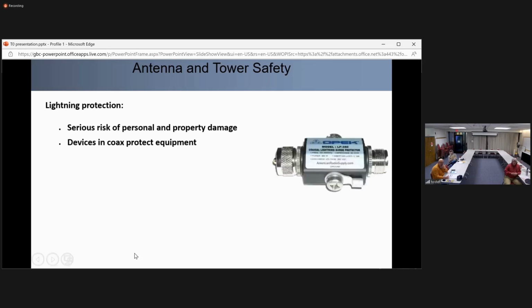And they're going to look something like this. Cable goes in one end, comes out the other. You'll notice there's a big screw on the side with a big fat tab on it. That's the grounding strap. So these would be mounted in the coax. They are mounted to a grounded panel, and that panel is usually located near the entrance to the structure. So you want to suppress any lightning surge before it enters the structure. So you'll mount those lightning surge protectors, as it says there on the device, to a grounded panel near the entrance to the structure.